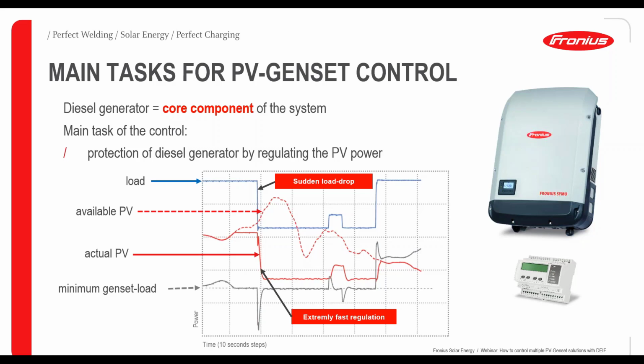Underneath we can see this schematic. With the blue line we can see the load profile, and then we can see a sudden load drop, for example, heavy machinery is switched off, and in the red area we would see the available PV in the dotted line. But because we need to make sure that the minimum genset load, the gray line, is not exceeded down below, we need to cut down the actual PV power. This is done in milliseconds. It's a very fast regulation, and therefore the genset will not run underneath a certain efficiency level. This is done by the control.